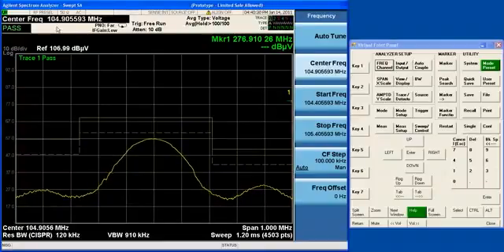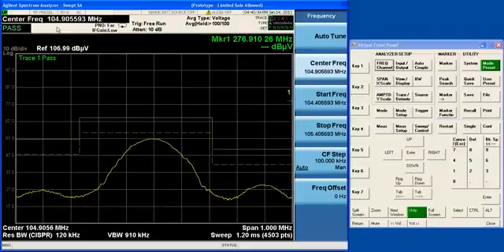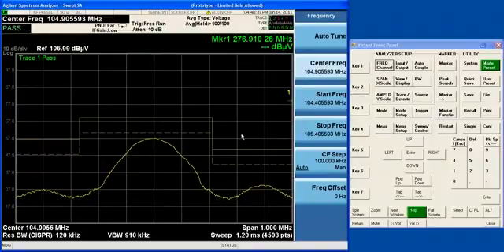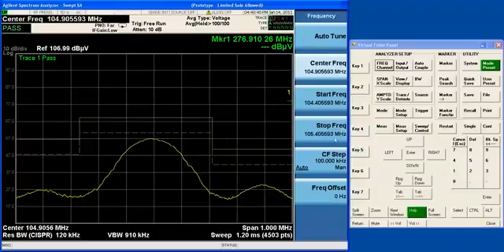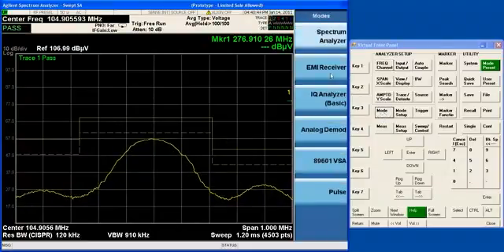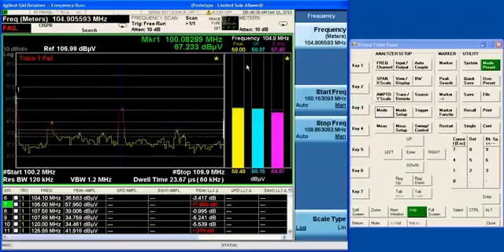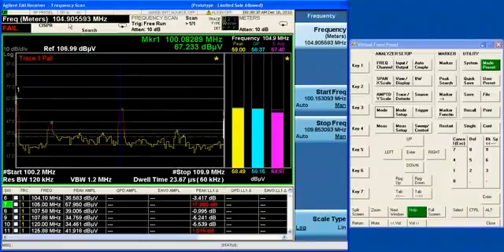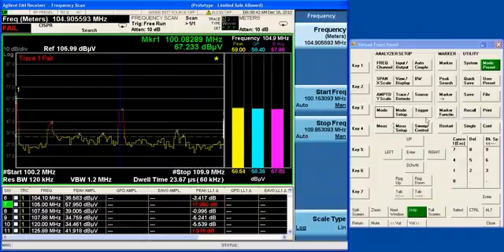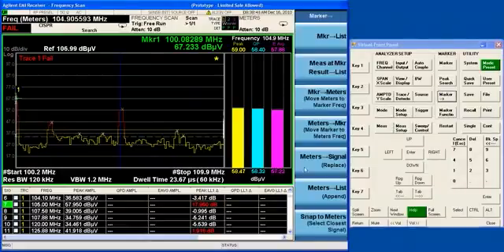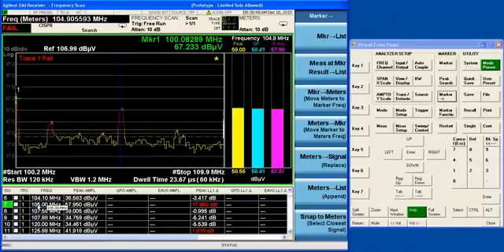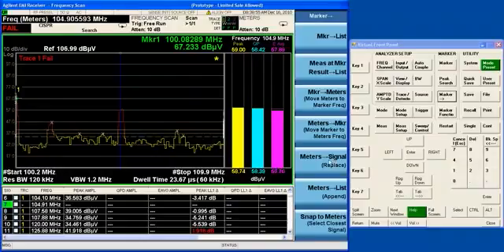So now that we've got our updated frequency, watch what happens when I go back to the EMI receiver. Watch that frequency. It's the same as it was when I was in the spectrum analyzer app. And now I can, using the marker to function, I can replace the value of signal number 7 with this new updated value by doing a meters to signal replace function.